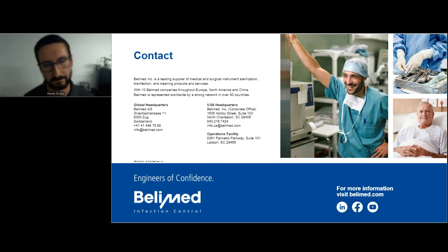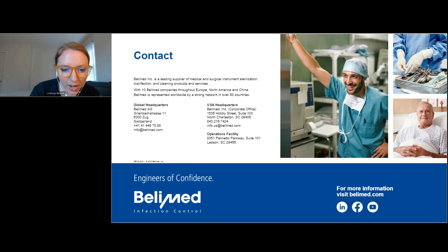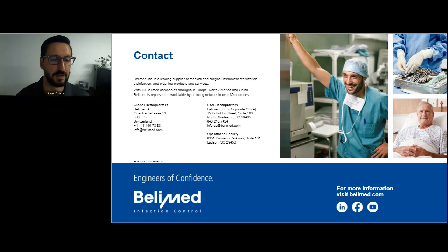The next question: do you recommend a one-way workflow for staff into and out of decontam? I've never seen that flow in the medical field. You have staff coming in one direction and leaving in another — that's difficult to do, particularly because we're already fighting for space just to get a vestibule for staff to gown up properly. I have seen spaces restricted from different areas where you may have a door but you're not allowed to enter it. But we don't typically see true one-way staff entrance and exits in decontamination in the US.